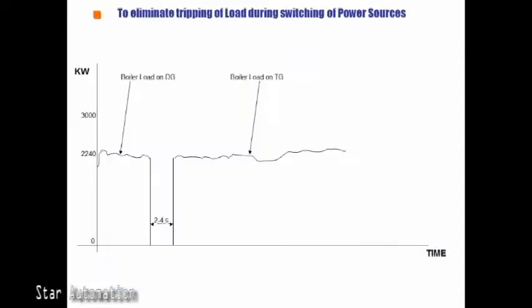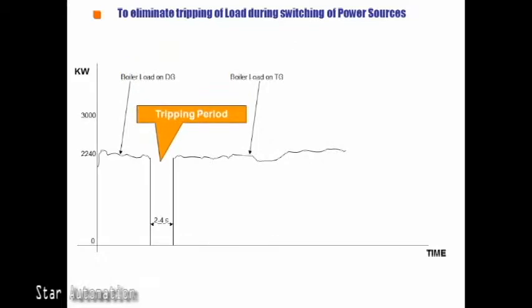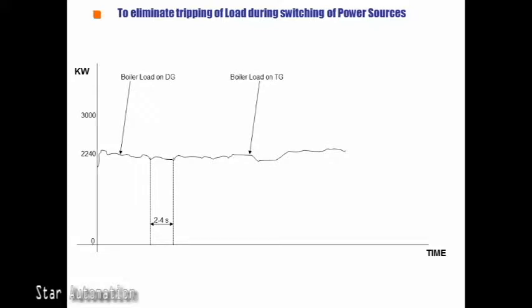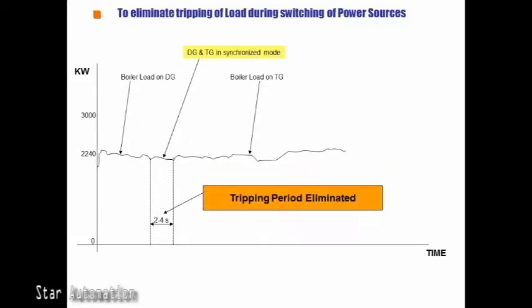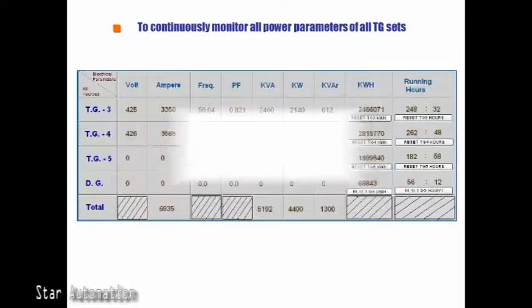In the sugar mill, the first boiler is started with the help of a diesel generator set. The boiler then generates steam which is used to start the TG set. When the TG set's voltage is built up, there is a need to shift the boiler's supply power from the DG set to the TG set. This is where DG and TG power synchronization is required, so that there is no tripping during power switchover.